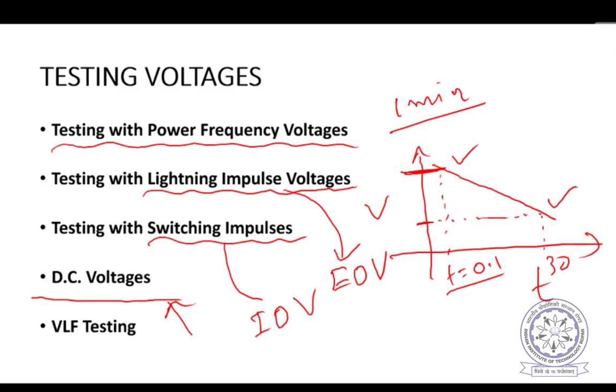So what will happen when we test under AC voltage, it will absorb large reactive power. Testing is very difficult from a laboratory voltage source, and supplying so much reactive power is not possible. Therefore, testing under DC voltages will also be carried out, because under DC voltage the cable behaves as an open circuit, so there will be no current except during the transition. That's why DC voltage tests are carried out even for AC cables.